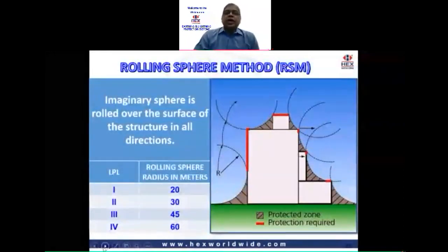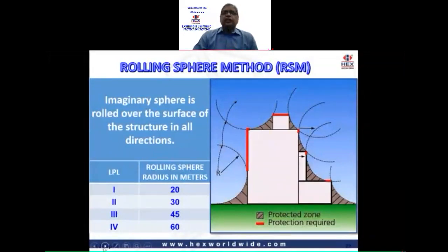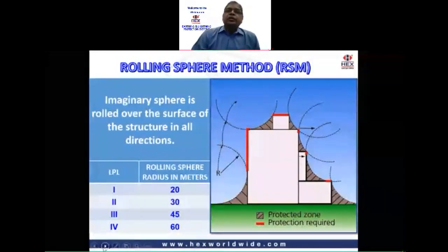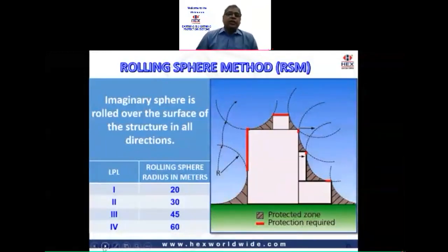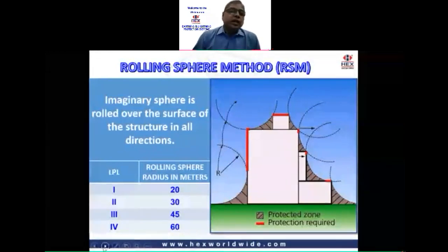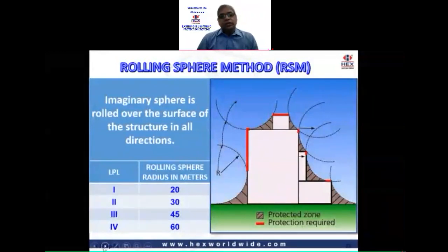Now, method one, RSM, states that a large imaginary sphere or ball is rolled over the surface of the entire structure to be protected. It has to be rolled in all directions. It's easier said than done. Wherever the ball touches the structure, that area needs to be protected, as you can see from the slide. The radius of the sphere is as given in the table according to the lightning protection level. So if I use lightning protection level 1, you have to roll a sphere of 20 meters radius. Level 2 is 30, level 3 is 45, and level 4 is 60.